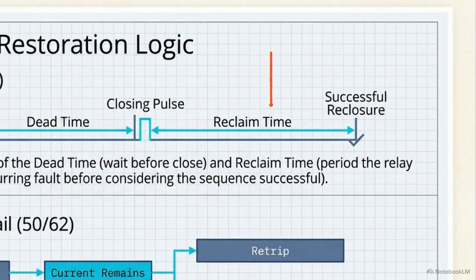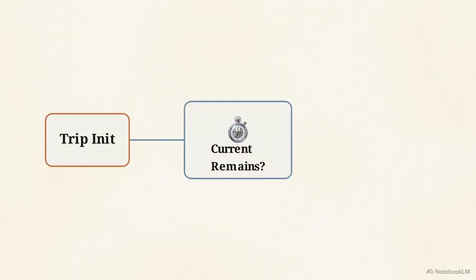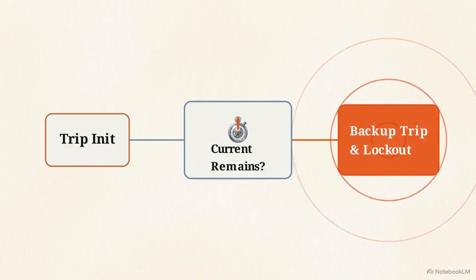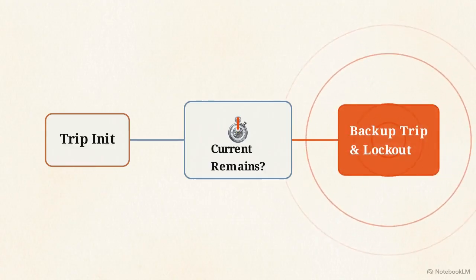The bottom half displays the circuit breaker fail logic. Technicians simulate a scenario where a mechanical trip initiates, but the injection set continues feeding current. The logic must recognize the breaker is stuck, triggering a timer to execute a backup trip to all adjacent breakers.